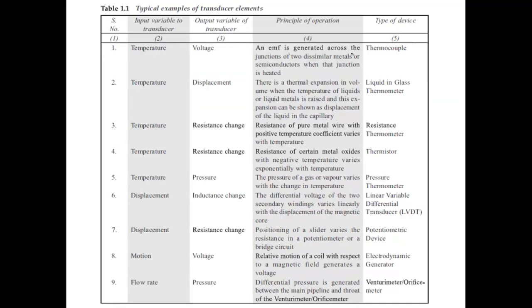These are typical examples of transducer elements. For the liquid-in-glass thermometer, the principle is thermal expansion in volume when the temperature of liquids or liquid metals is raised, and this expansion is shown as displacement of the liquid in the capillary. So the input variable to the transducer is the temperature of the fluid, and the output variable is displacement. For the resistance thermometer, a pure metal wire with positive temperature coefficient has resistance varying with temperature — input is temperature, output is resistance change.